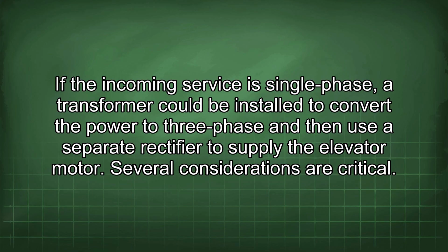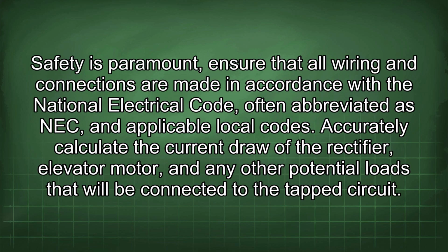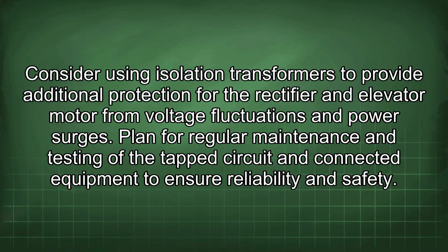Several considerations are critical. Safety is paramount. Ensure that all wiring and connections are made in accordance with the National Electrical Code, often abbreviated as NEC, and applicable local codes. Accurately calculate the current draw of the rectifier, elevator motor, and any other potential loads that will be connected to the tapped circuit. Consider using isolation transformers to provide additional protection for the rectifier and elevator motor from voltage fluctuations and power surges. Plan for regular maintenance and testing of the tapped circuits and connected equipment to ensure reliability and safety.